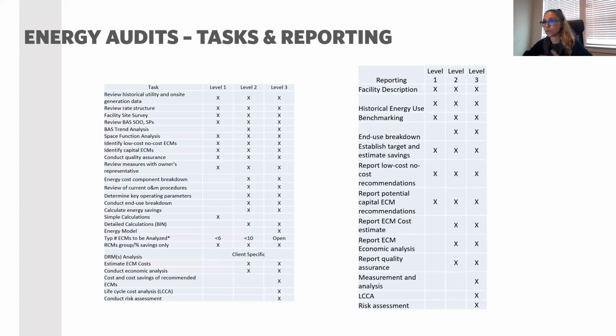So for example, for all audits, they review historical data, construction drawings or available BAS information, space functions, and things like that. This is required for all levels. But BAS trend review is required for level 2 and 3 audits. In terms of calculations, simple calculations are okay for level 1, but bin calculations, which I will get into in the upcoming slides, are required for level 2, and energy models are required for level 3 audits. Life cycle cost analysis, for example, is also required for level 3 audits.